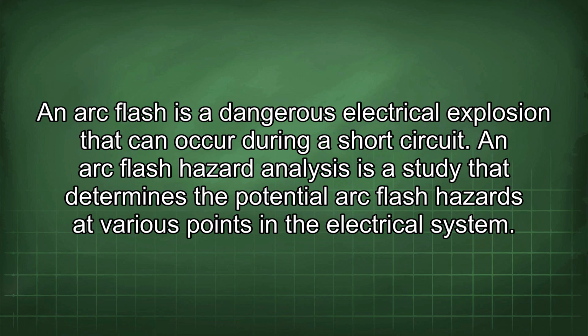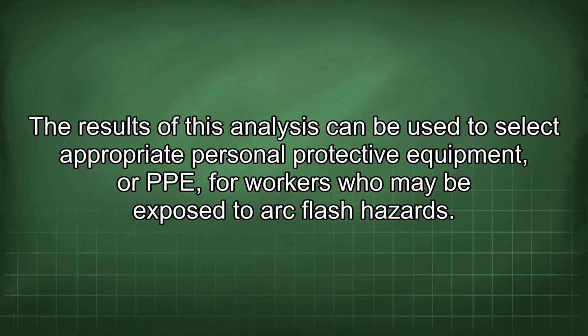An arc flash is a dangerous electrical explosion that can occur during a short circuit. An arc flash hazard analysis is a study that determines the potential arc flash hazards at various points in the electrical system. The results of this analysis can be used to select appropriate personal protective equipment, or PPE, for workers who may be exposed to arc flash hazards.